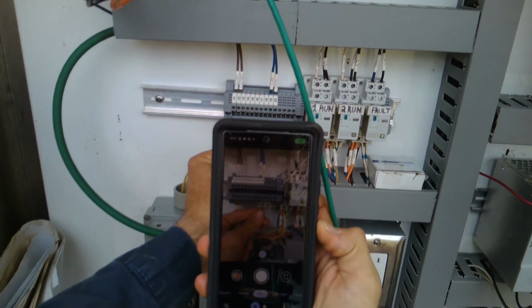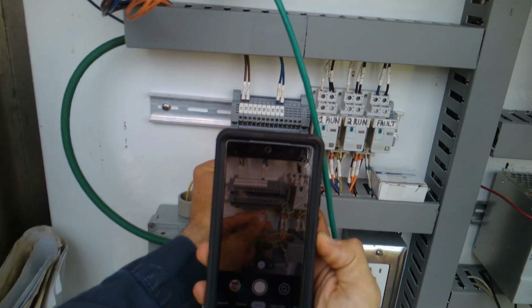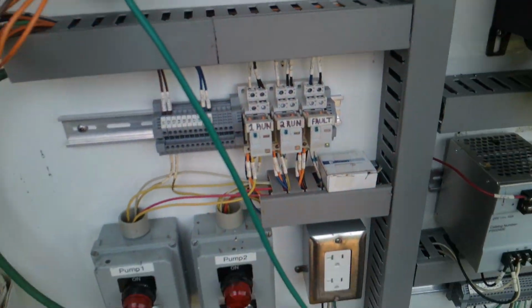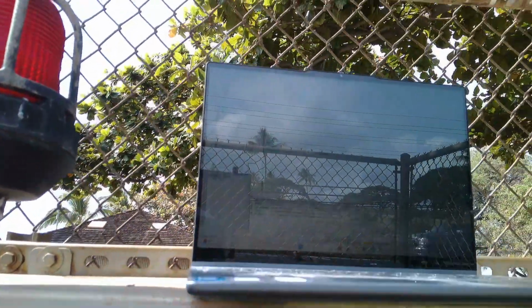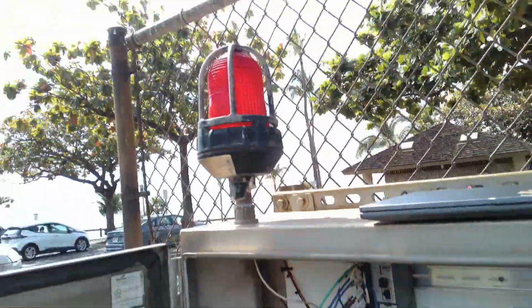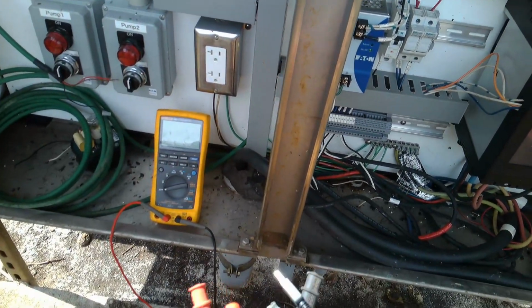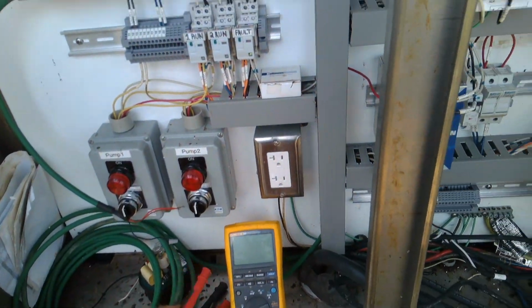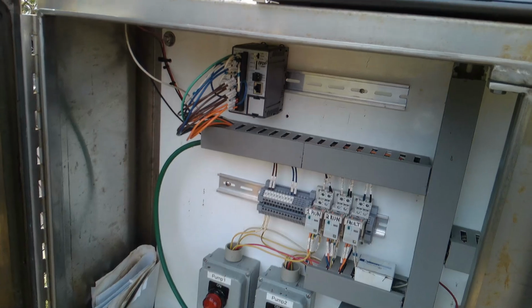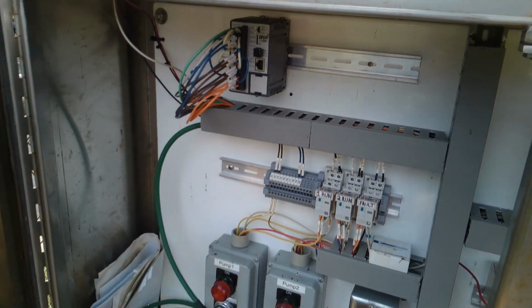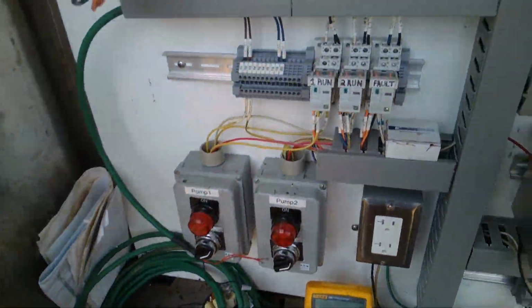Take a photo for the operator, so if they are the ones who change it out, they can put the wire back on there. And if they call me, I can just text them that picture. We can disconnect our laptop. If we don't connect the transducer, it's going to stay in a fault mode and the strobe is going to keep flashing. So I need to let the operator know why the strobe is flashing. And then it will switch over to float mode and run after that. Basically, the strobe is alerting them that the transducer is damaged.